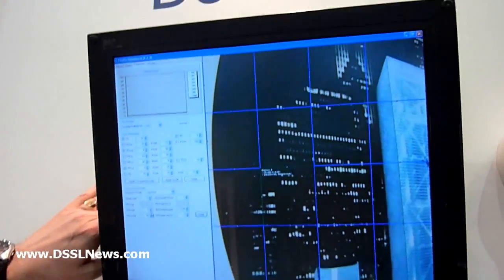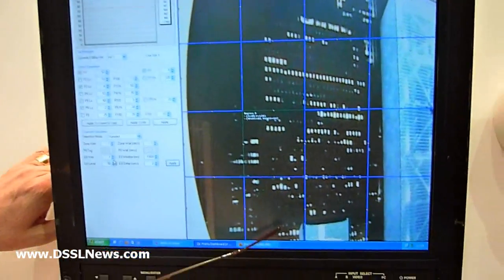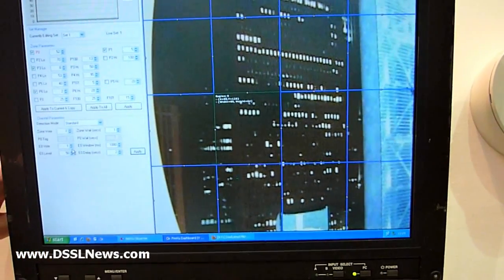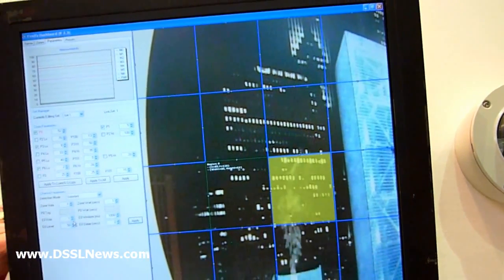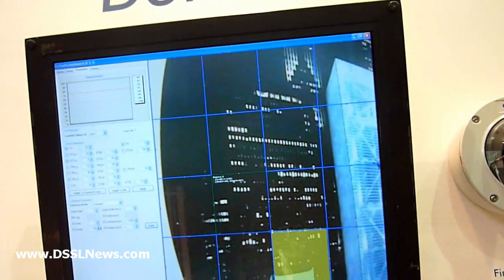You can actually see the smoke — notice how the smoke is actually coming up here. There's the smoke, that's causing activation there — now it's gone red, so that's causing activation using existing CCTV cameras. That's video smoke detection.